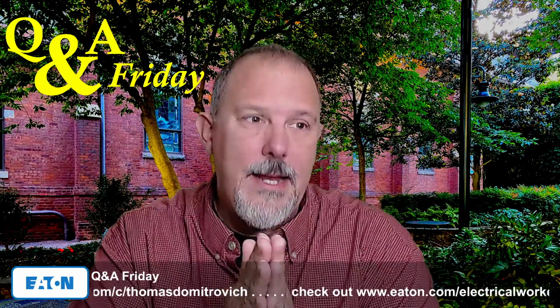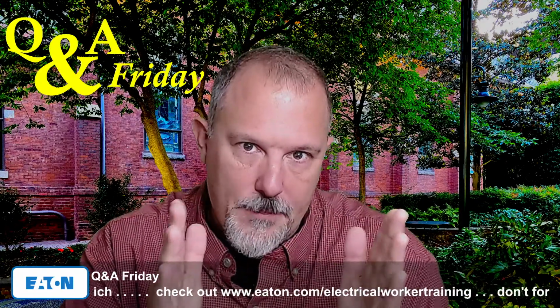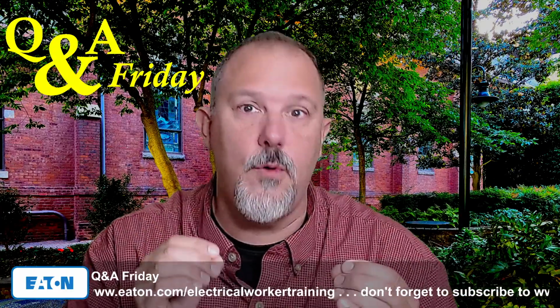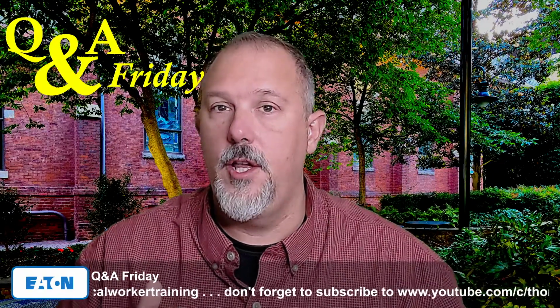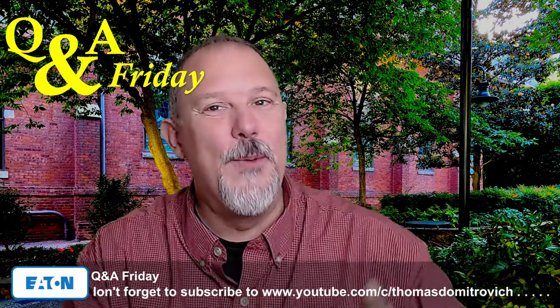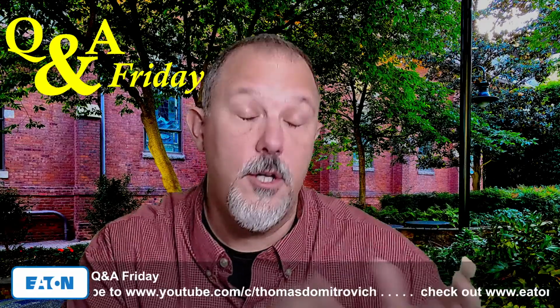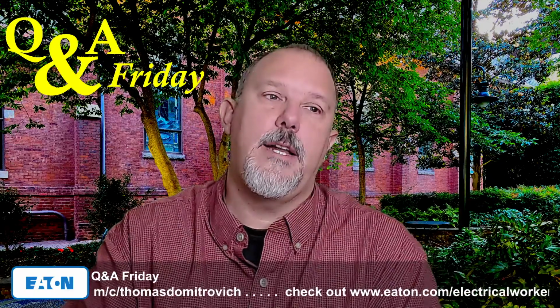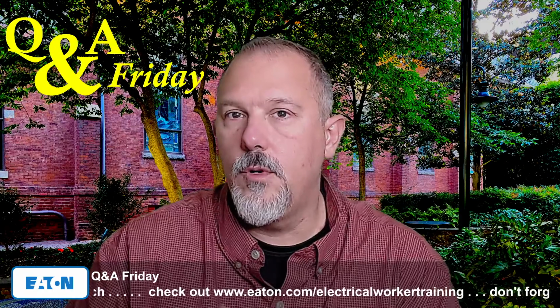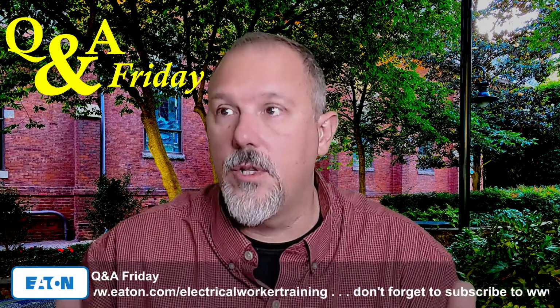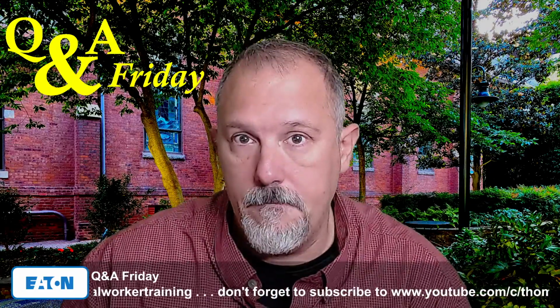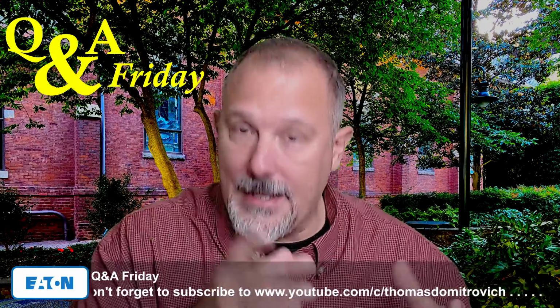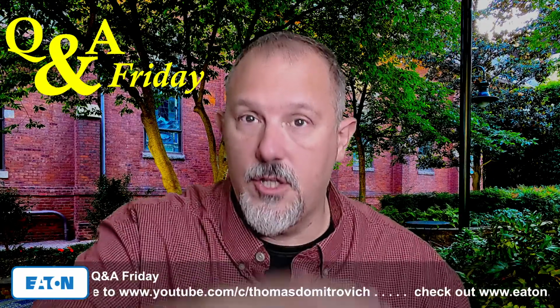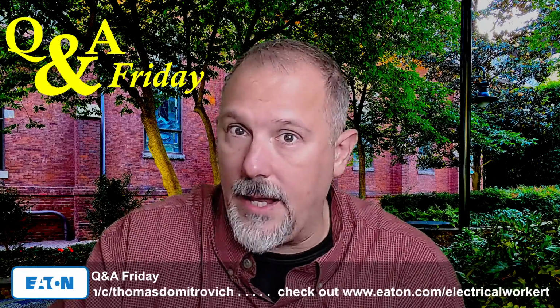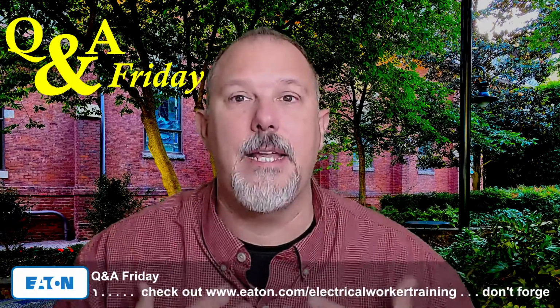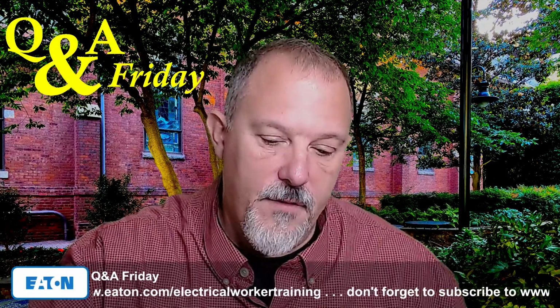Why is that important? Because when a device downstream begins to separate the contacts, I'm adding a dynamic impedance, which overall reduces the fault current that I'm trying to interrupt, which will impact the response time of the upstream overcurrent device. So, in general, whenever you're looking at protecting a piece of equipment, we'll use the terms dynamic or static devices. What's a good example of a static device? If I have a fusible switch in front of a busway, and the busway has a rating of, say, 10K, I can use up, over, and down to show the RMS current that will pass through the busway is reduced. The busway is not actively trying to open, it's just withstanding and trying to carry the current. So I can use that method to say I am reducing the fault current for that bus.